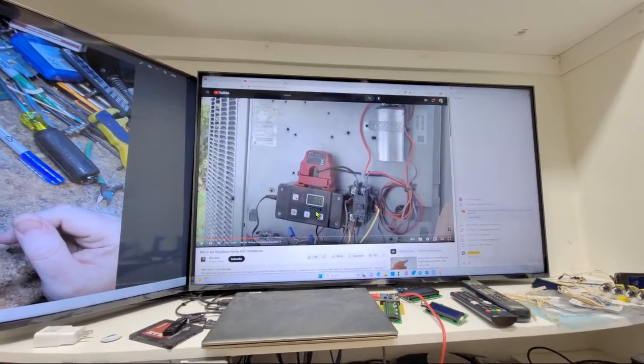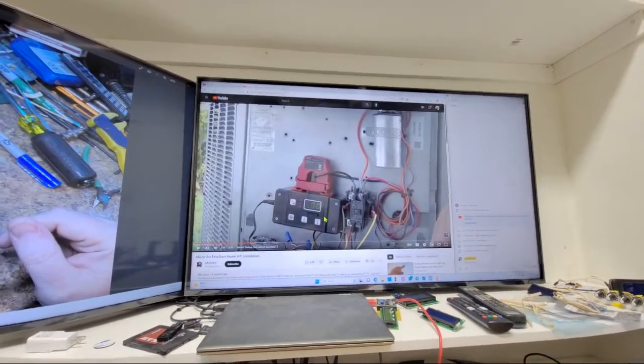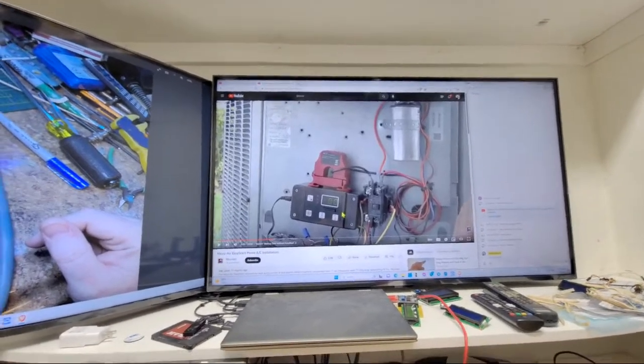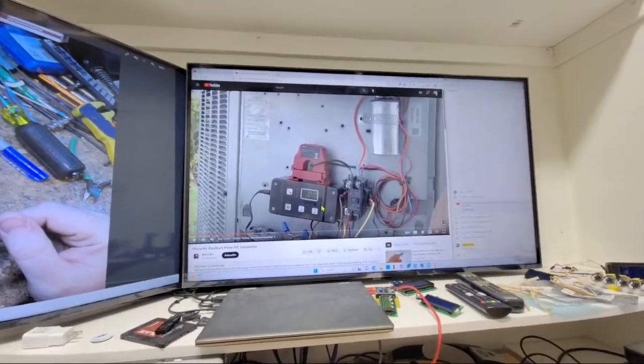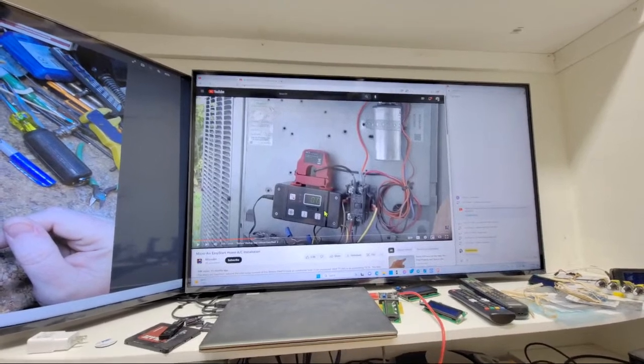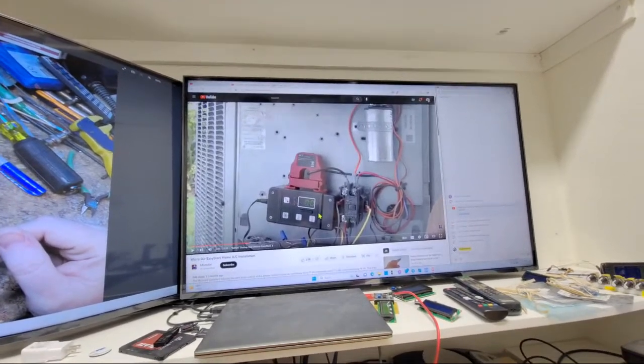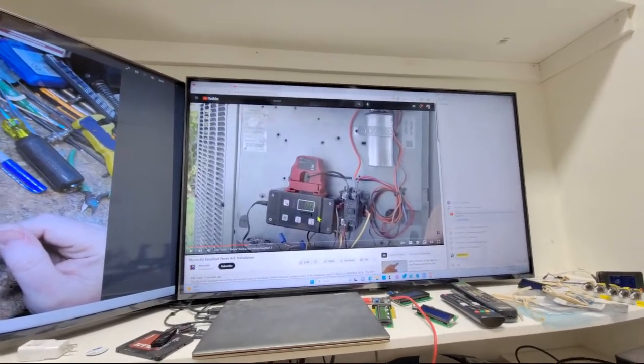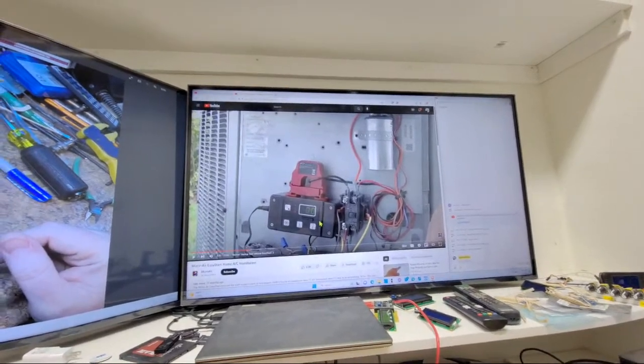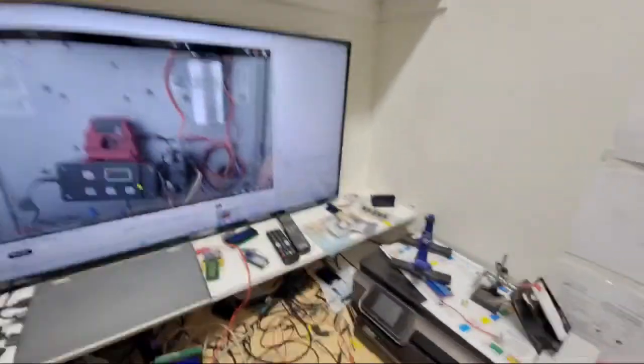But this seems to just be capturing your inrush. Now I'll say what this guy's doing, I've noticed the exact same thing. It is a comparison, but it's just not the same as looking at your instantaneous locked rotor amps, your peak inrush, and then how it ramps down with the sine wave. I guess I should have pulled up a diagram, but somebody says Rheem, I don't know, it sure looks like a Goodman.